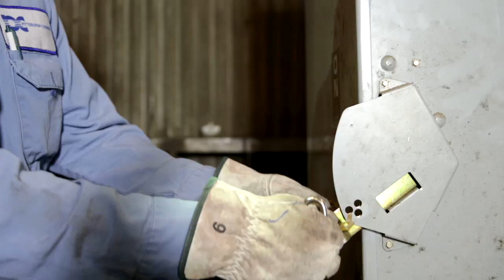Well, then when we got done, we went out to turn the transformer on. We were going to turn on the switch rack to turn on lights because it's dark in the plant. And when we come back in from turning on that switch, we noticed that both sets - the top and the bottom, line side and the load side - were lit up.